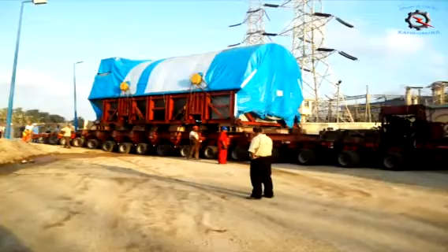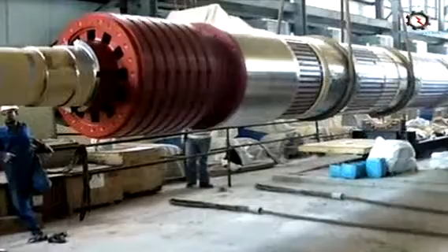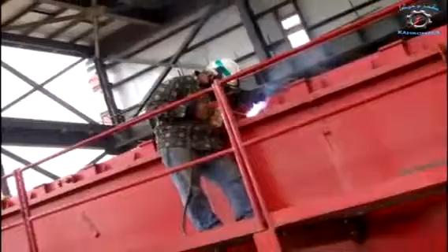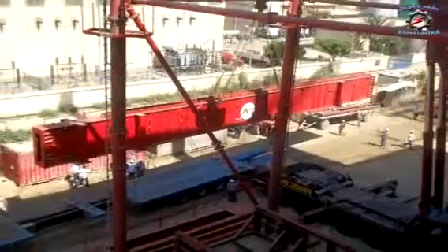The generator contains two main parts: the stationary stator, about 400 tons, and the spinning rotor, about 90 tons. Kahromika successfully installed the generator parts efficiently, whereas the stator was lifted up to turbine level, 15 meters elevation, by an advanced lifting system performed by ALE Company, one of the most specialist companies in the world in heavy lifting, under complete technical supervision by Kahromika.